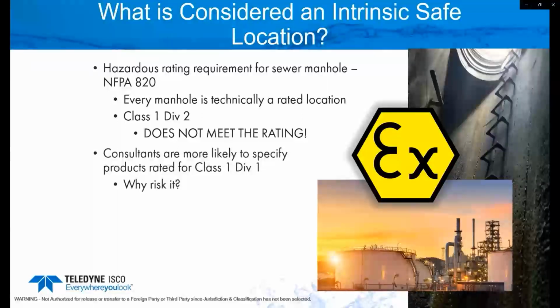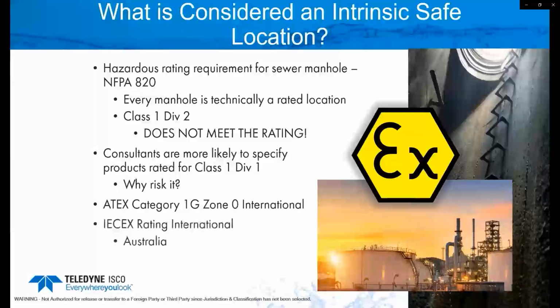We're also seeing more in the industry where consultants are more likely to specify a Class I Division I product — the main reason being, why take a chance? The cost difference between an intrinsic safe product and a non-intrinsic safe one is really not that much, so people are more inclined not to take a chance and just play it safe, do it the right way. We also have approvals for ATEX Category 1G Zone 0, which is more international, Europe, but also the IECEx rating, international, primarily like Australia.